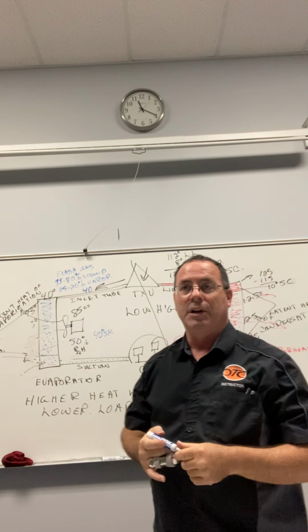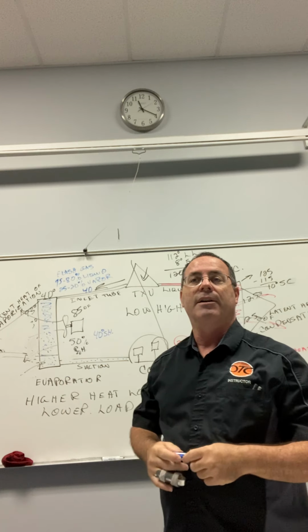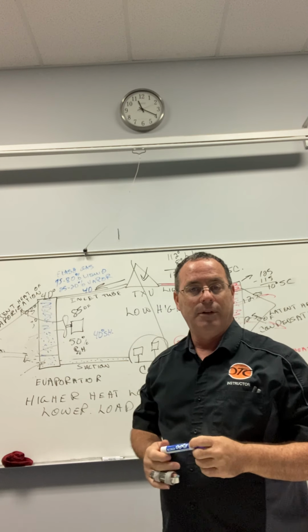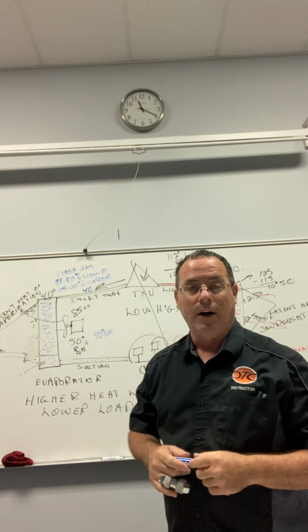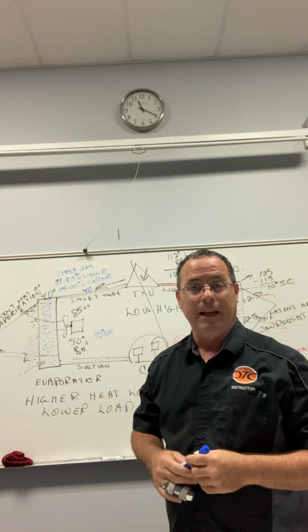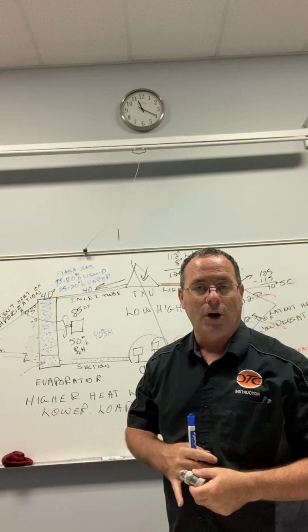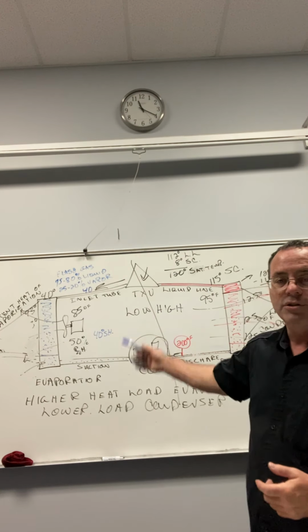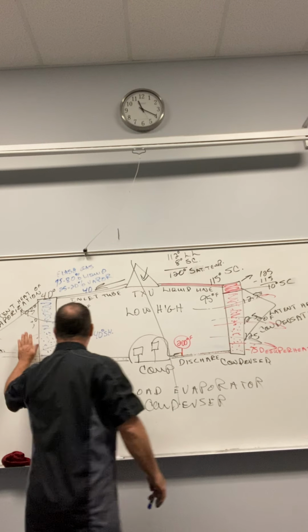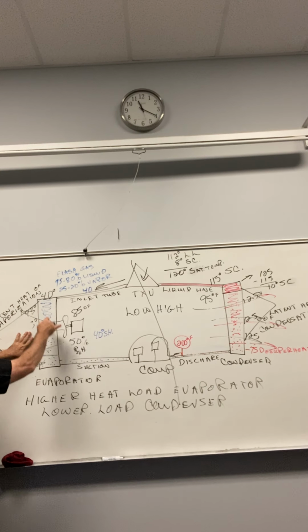Now, I told you before, you may have started a brand new unit in a very hot house. Or the house has been off for days because it's been broken and you turn it on. You may have high superheat. That doesn't mean the unit's not charged correctly. You have to wait a while for it to come down to adjust that charge. Okay? So anytime you have less refrigerant, higher heat load coming in here, it's going to boil off quicker.